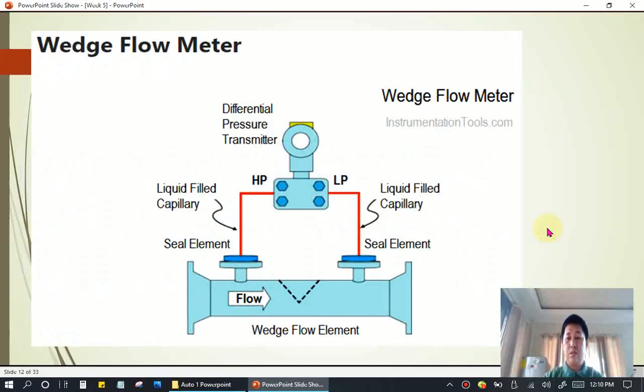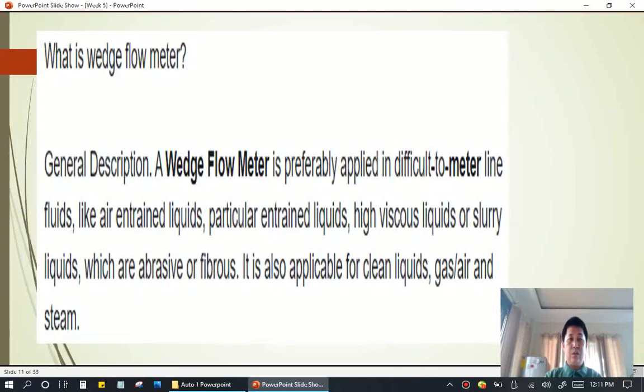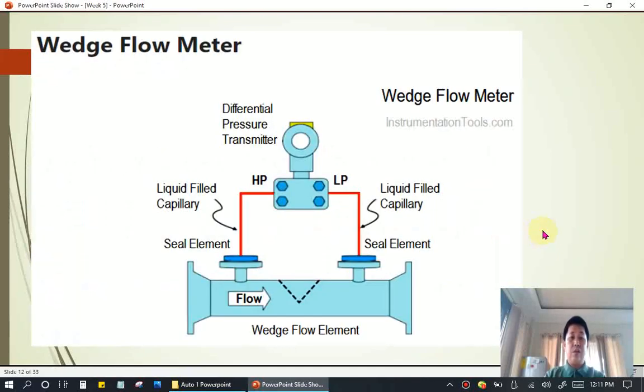Next, we have here the wedge flow meter. So what is a wedge flow meter? General description: a wedge flow meter is preferably applied in difficult to meter line fluids like air entrained liquids, particular entrained liquids, high viscous liquids, or slurry liquids which are abrasive or fibrous. It is applicable for clean liquids, gas, air, and steam. So here is the illustration, wedge flow meter.